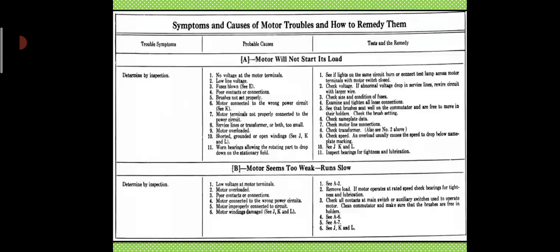Motor seems to be weak or runs slow. It is determined by inspection. The causes are low voltage at the motor terminals, motor overloaded, poor contacts or connections, motor connected to the wrong power circuit, motor improperly connected to the circuit, and motor winding damage. Then the tests and remedies are: remove load and see if the motor operates at rated speed, check bearings for tightness and lubrication, check all contacts at main switches or auxiliary switches used to operate the motor. Clean commutator and make sure that the brushes are free in holders.